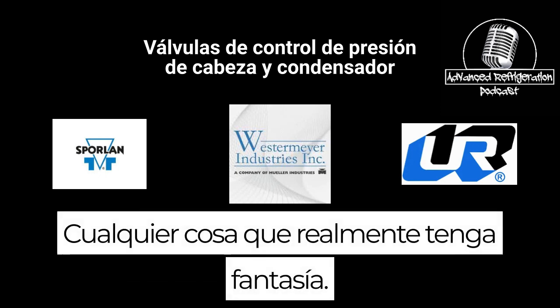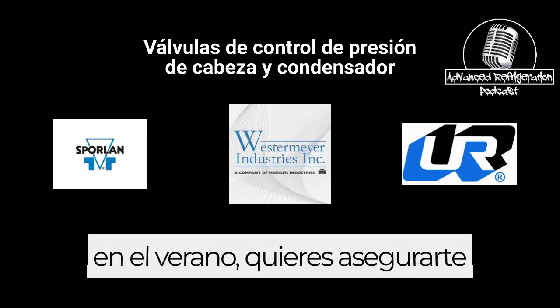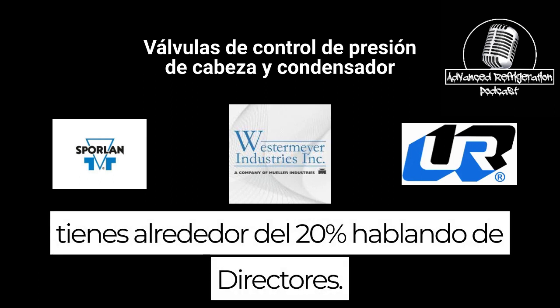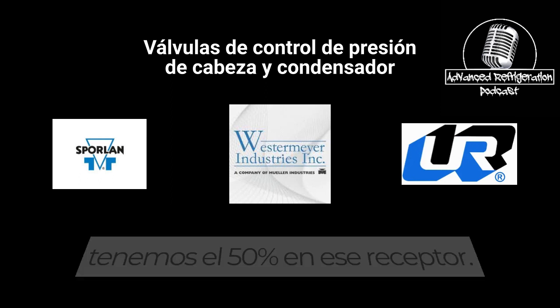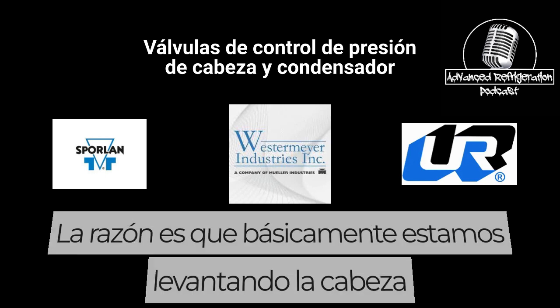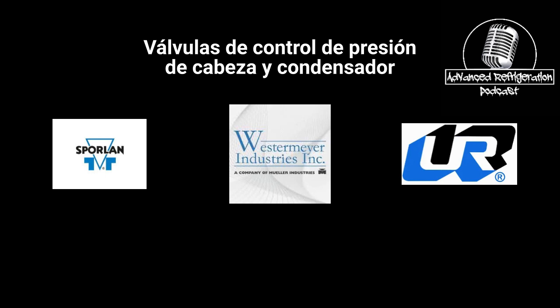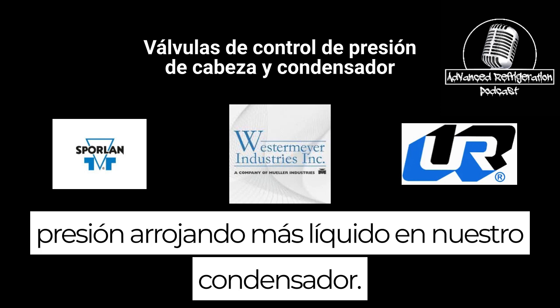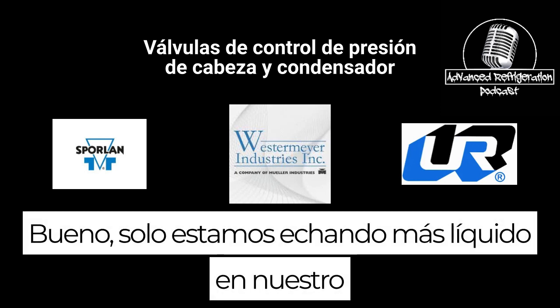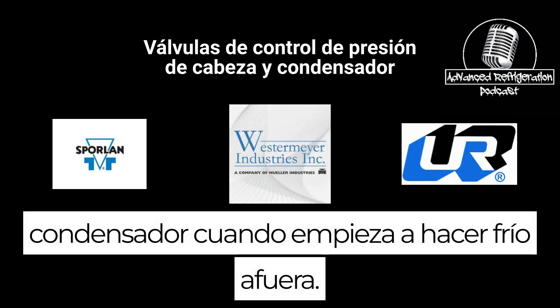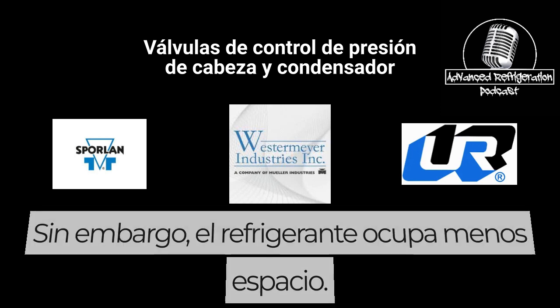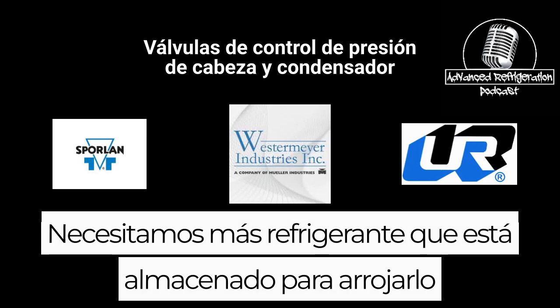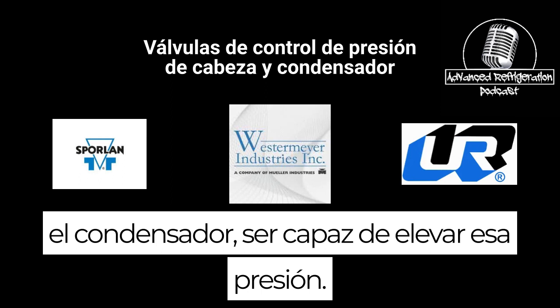The first system we were talking about was just fan cycling. Anything that has fan cycling, make sure you do have a full charge. In the summertime, you do want to make sure you have about 20%. Talking about headmasters now, we want to make sure that we have 50% in that receiver. The reason is that we're raising the head pressure by throwing more liquid into our condenser, and we're only throwing more liquid in our condenser when it starts getting cooler outside. The colder it gets, the tighter the molecules get in the refrigerant. The refrigerant takes up less space, so we need more refrigerant in storage to throw into the condenser to be able to raise up that pressure.